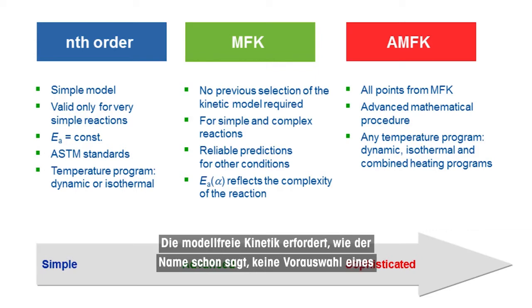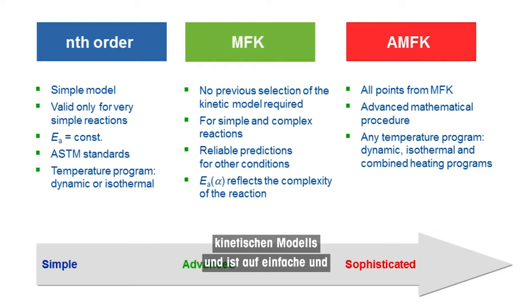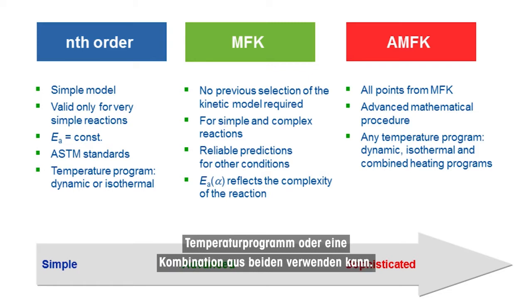Model Free Kinetics, as the name suggests, does not require a pre-selection of any kinetic model and is applicable to simple and complex reactions alike. The kinetic calculations are based on three or more dynamically measured conversion curves. Advanced Model Free Kinetics is the most sophisticated method of the three and extends the possibilities of MFK in that it can use any dynamic or isothermal temperature program or a combination of the two.